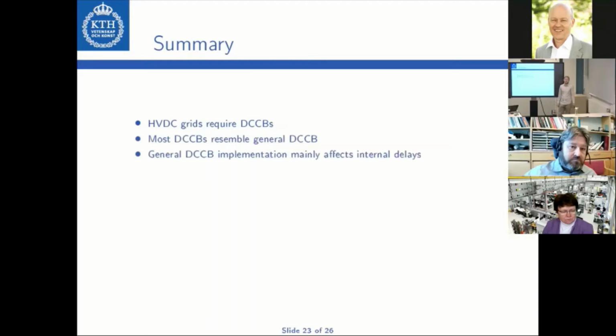Lastly, I would like to summarize. HVDC grids require DC circuit breakers. There are many DCCBs, but all of these resemble the general DCCB structure. How the general DCCB structure is implemented only affects internal commutation delays. As seen from the terminals, the characteristic current shapes and voltages can be observed. The major bottleneck and main source of delay is always the mechanical switch, and this cannot be avoided in HVDC applications.